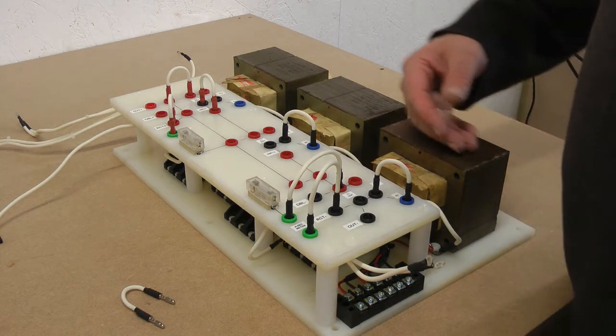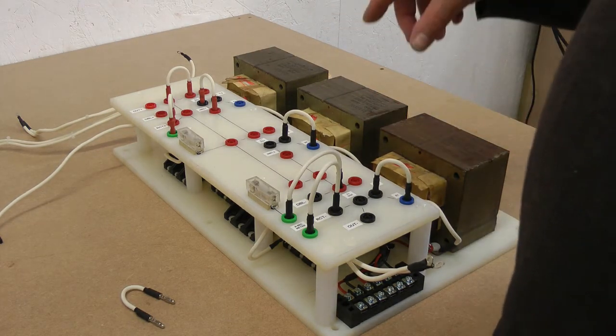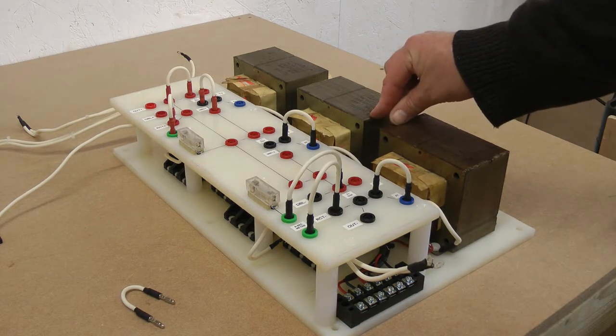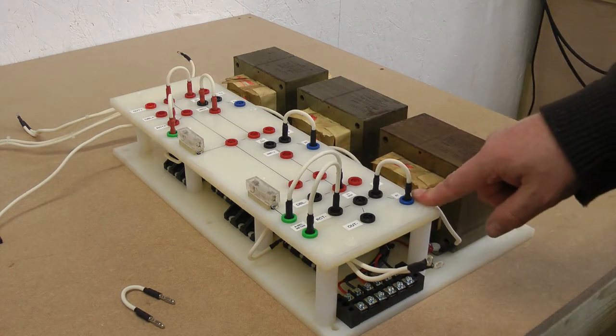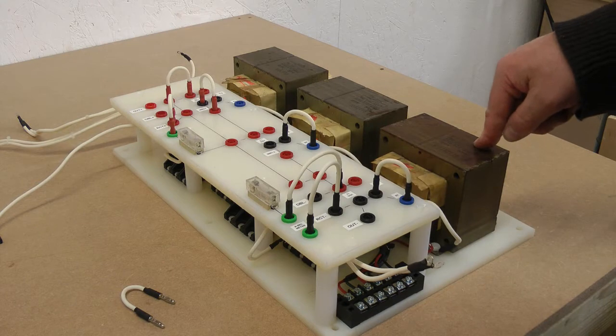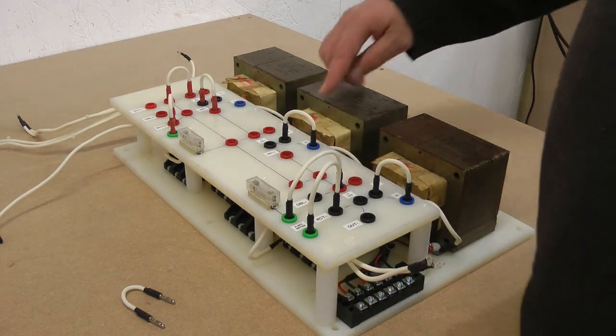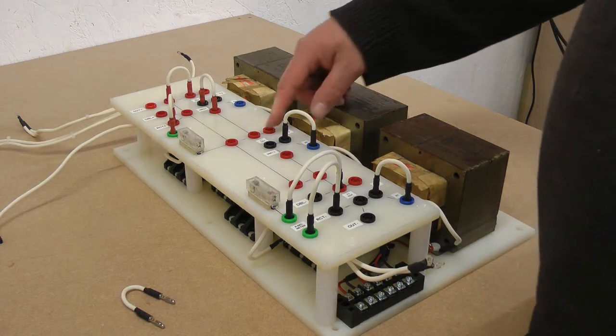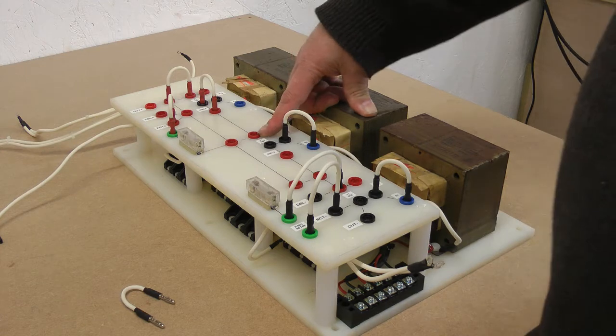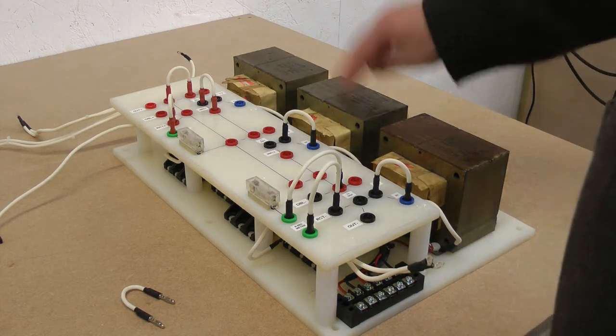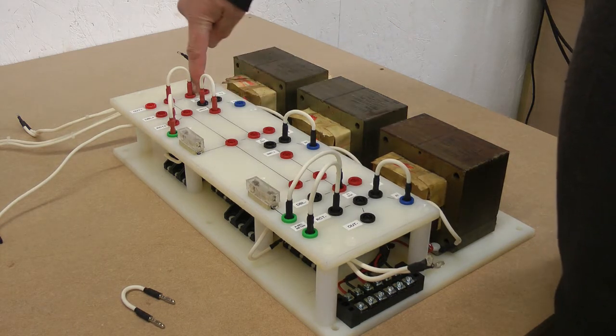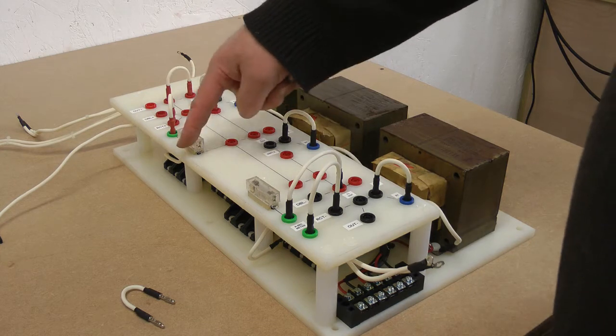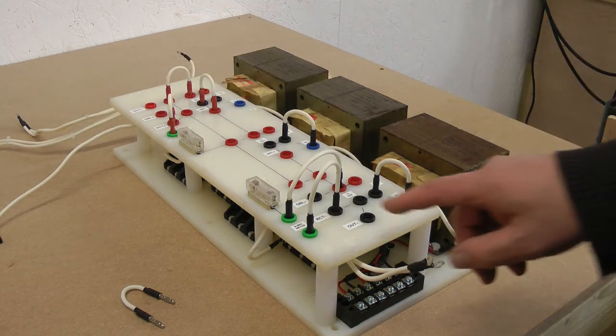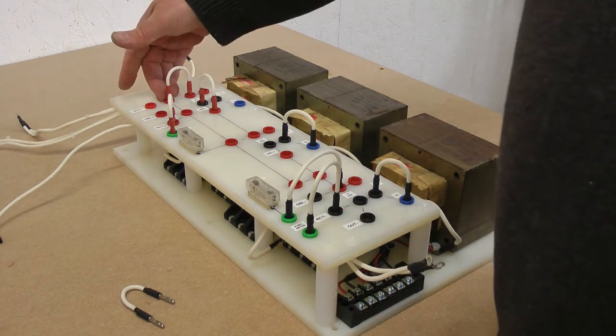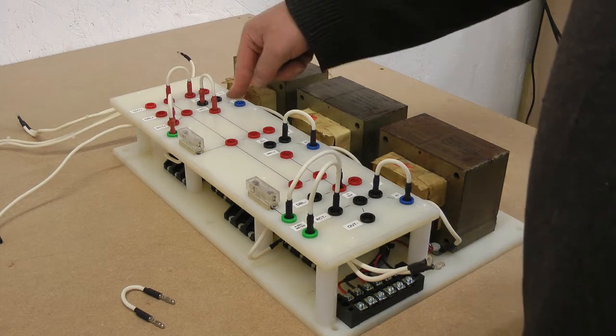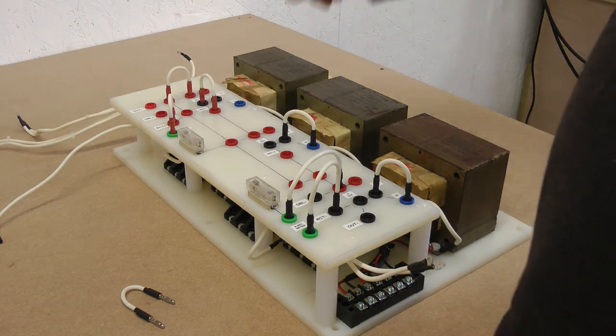Now we've got all three of these in series with these two cores connected together and through E1 and E2. This end comes down through the correct selection of the phasing to minus 3 kilovolts. This one with the opposite phasing connection will come up to plus 3 kilovolts. This one with the same primary phasing as this one will bring it up to plus 6 kilovolts. That comes out of this output line through here and into the rectifier. So this end is at minus 3 kilovolts, this end is at plus 6 kilovolts, and we do not have the line supply, the transformer earth supply connected to the line supply.